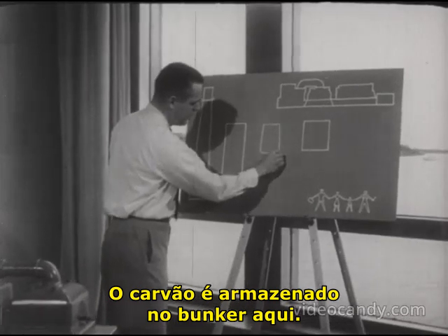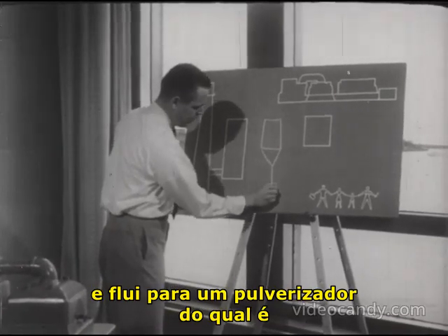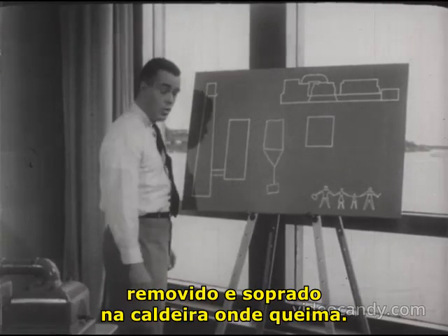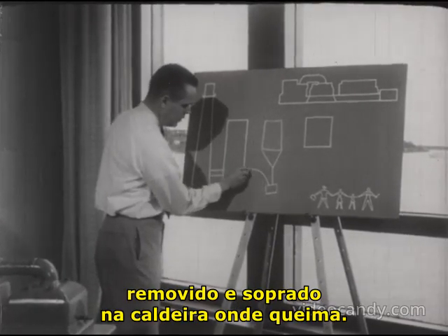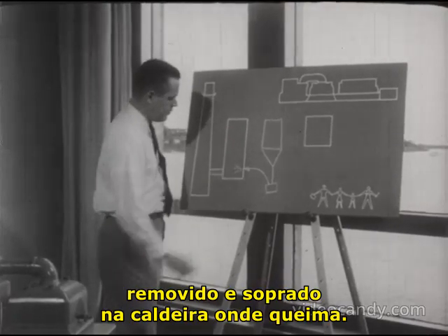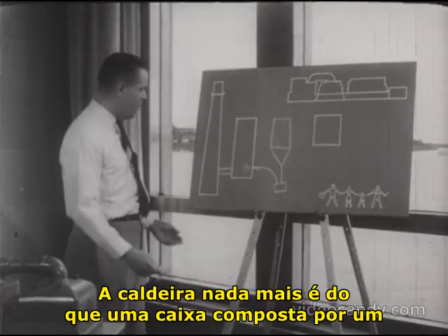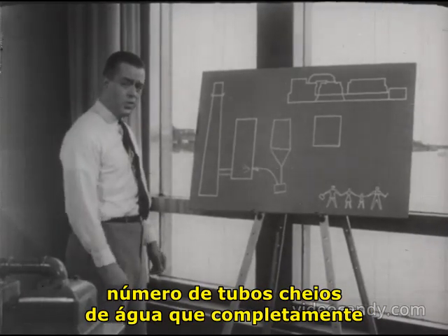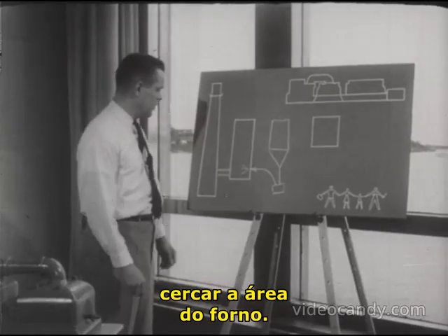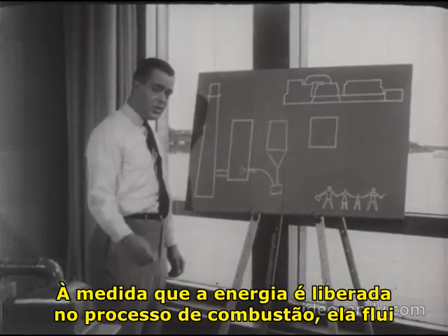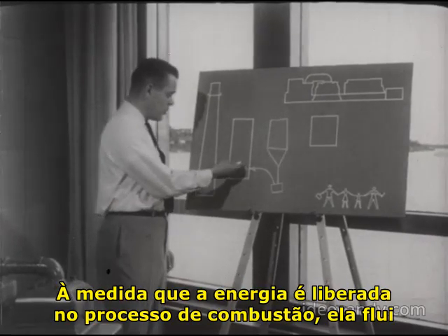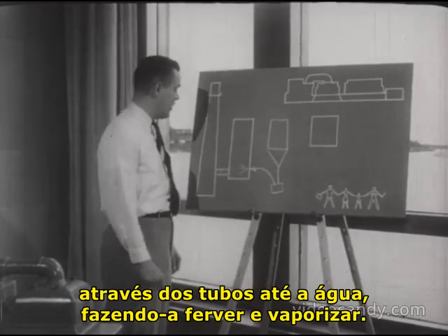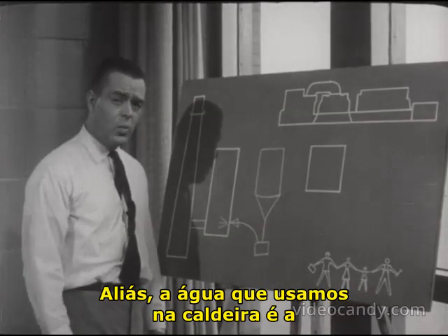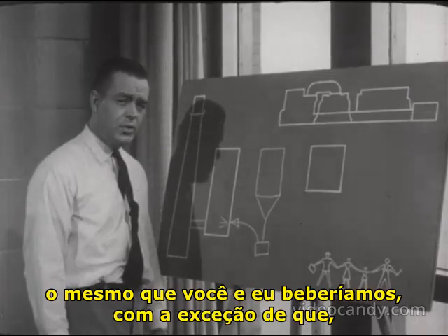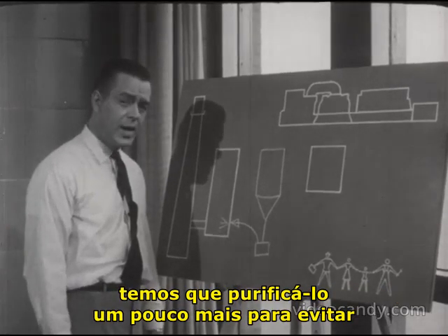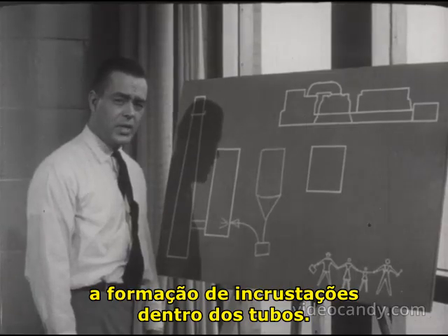Coal is stored in the bunker here and flows down into a pulverizer, from which it is removed and blown into the boiler, where it burns. Now, the boiler is nothing more than a box made up of a number of water-filled tubes that completely surround the furnace area. As energy is released in the combustion process, it flows through the tubes into the water, causing it to boil and vaporize. Incidentally, the water that we use in the boiler is the same as you and I would drink, with the exception that we have to purify it a little bit more in order to prevent the formation of scale inside the tubes.